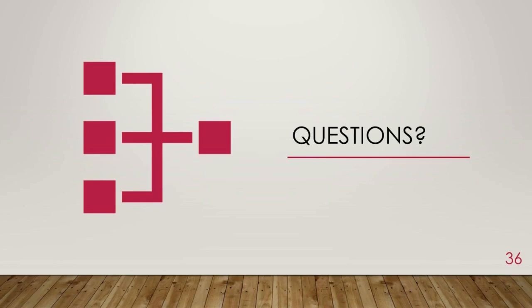Okay, the next question is, as part of the requirements for confirming that buildings comply with 90.1, will CXAs be required to review and accept and/or reject energy models for designs that are not following the prescriptive path? The only commissioning requirements added related to the performance path is that if you do something there, let's say you have some innovative new storage system or something that's not covered in the design, you would have to provide reasonable commissioning testing of that technology or controls to verify that it worked as part of your commissioning process. Again, if your building is of the size that commissioning is required. I hope that answers that question.